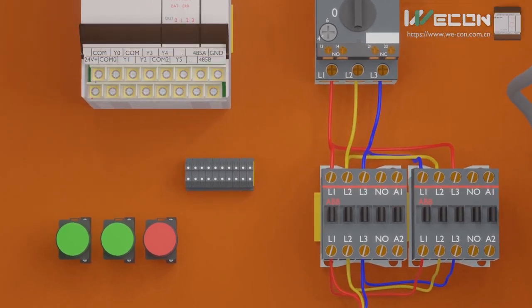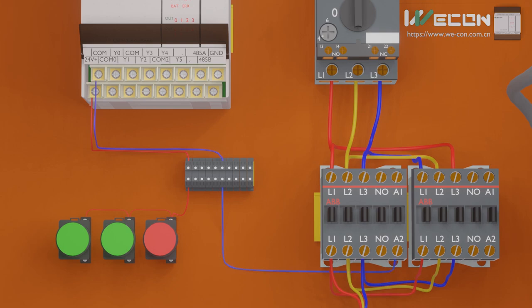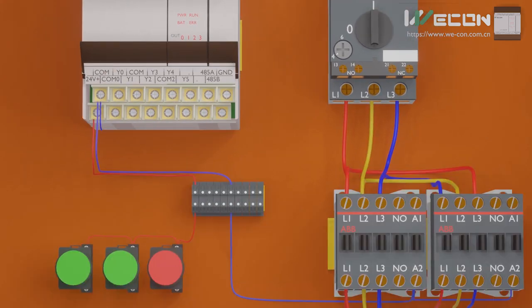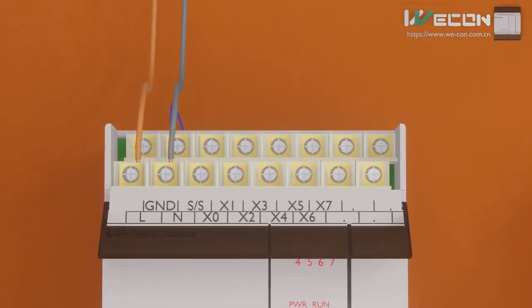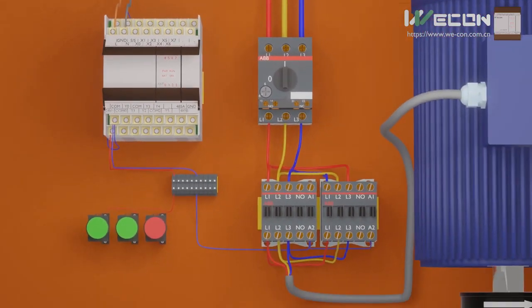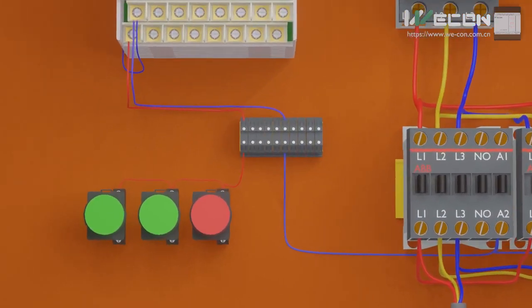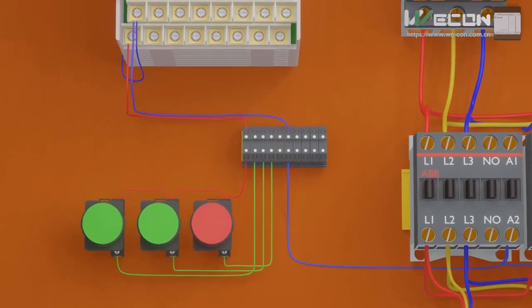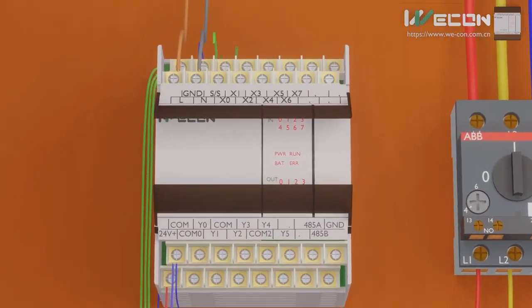This Wecon PLC has an internal 24V DC power supply which we can use to power a few of the input and output devices. First, we connect a red wire from the positive terminal of the power supply to one end of all the pushbuttons. Next, we connect a blue wire from the common terminal of the power supply to the A2 terminals of both contactors, and another blue wire from the common terminal to the SS terminal of the PLC. Then we connect wires from the other end of the pushbuttons to PLC input terminals X0, X1, and X2.